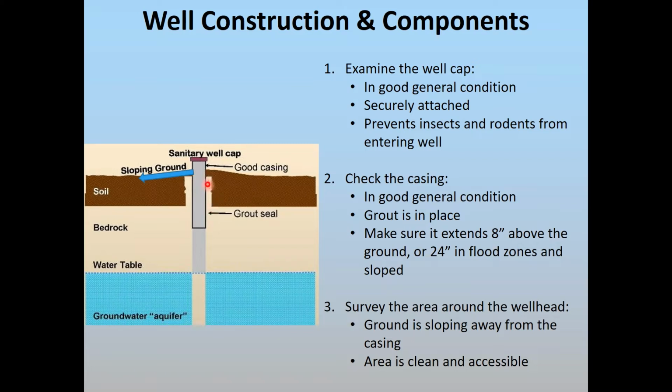And grout is basically a specialized clay, like a bentonite clay, that's packed in around the perimeter of the casing. And what that does is it helps to seal any sort of surface water that might try to follow the outside perimeter of the casing down into the well, potentially contaminating the well. So again, make sure your well cap is in good order, make sure the ground slopes away from your wellhead, and grout seal is in good shape.